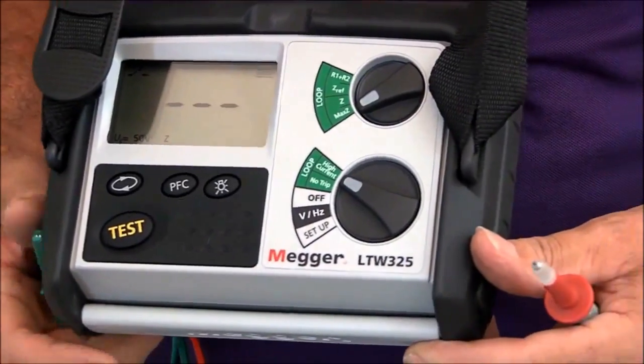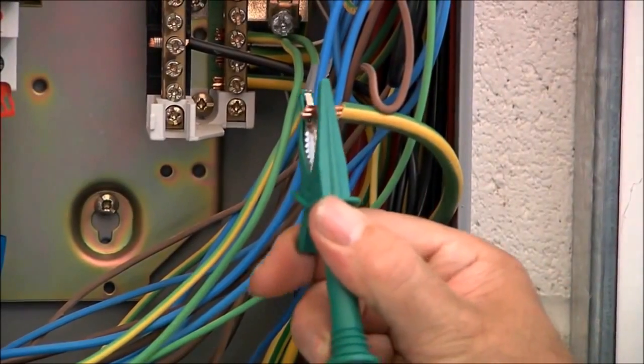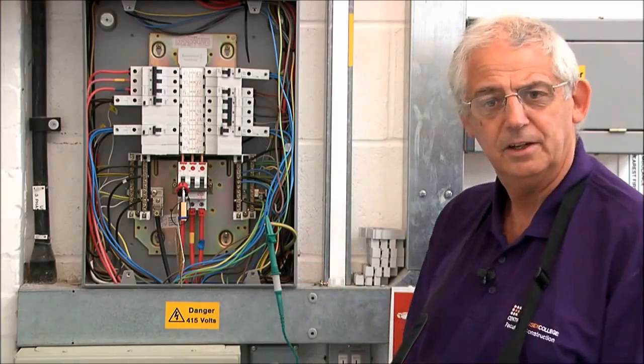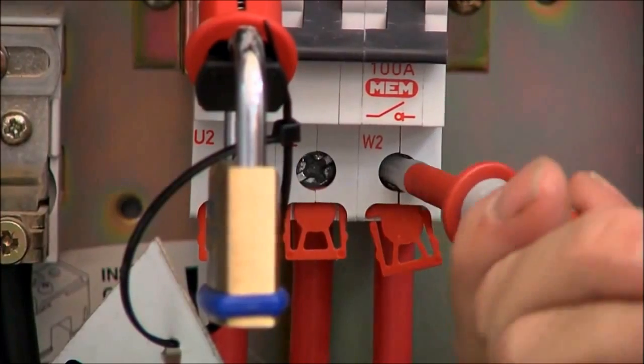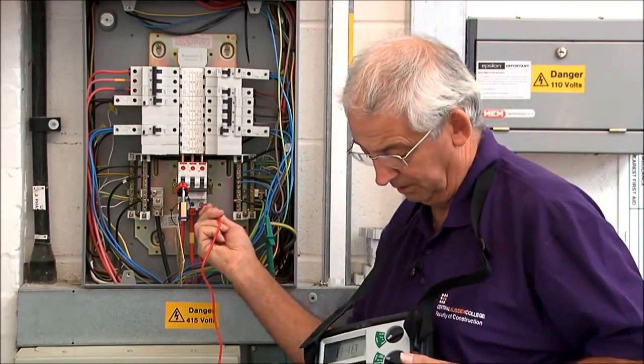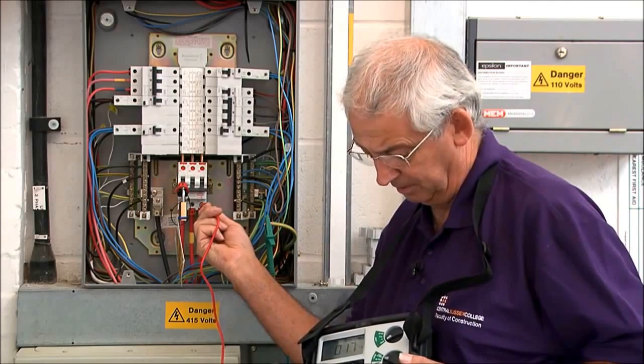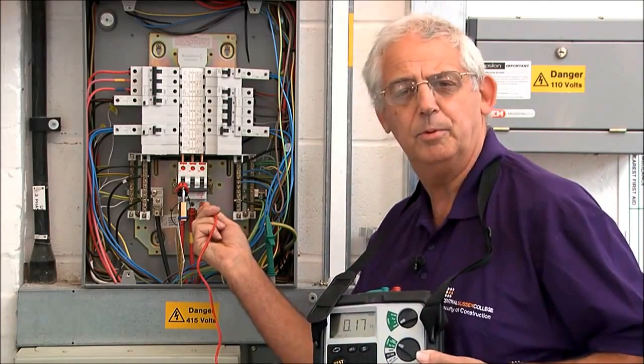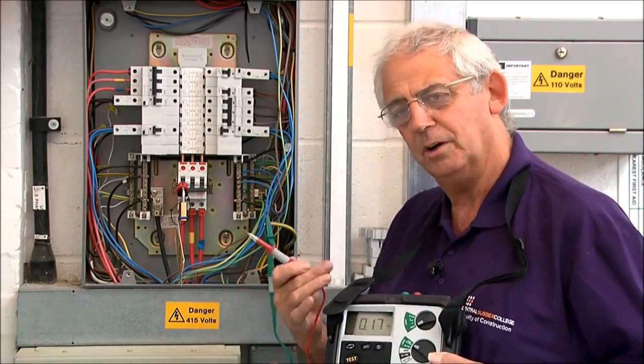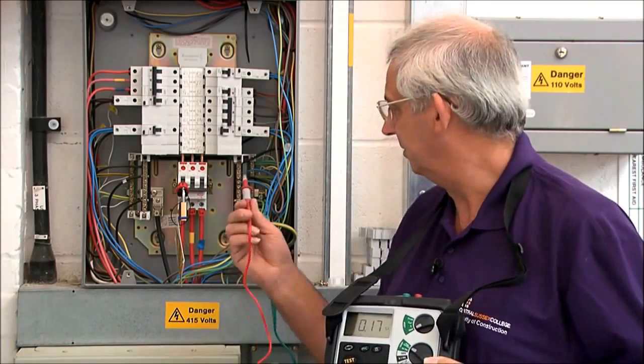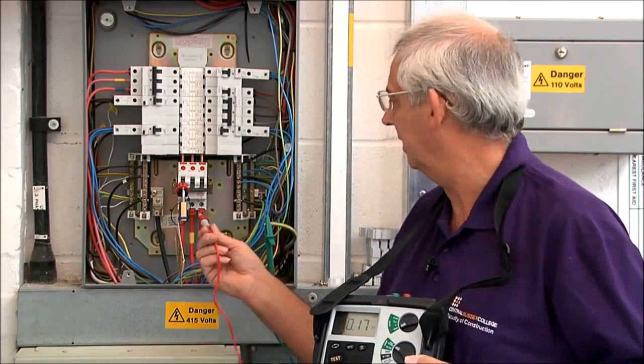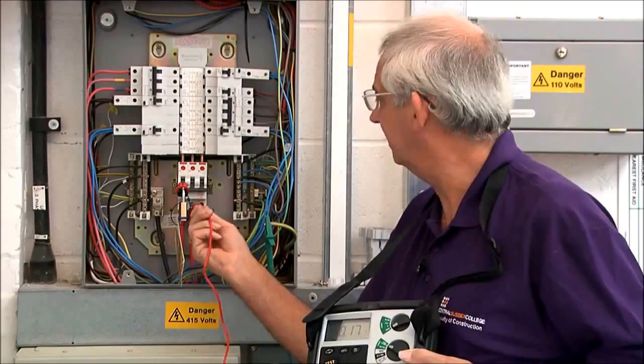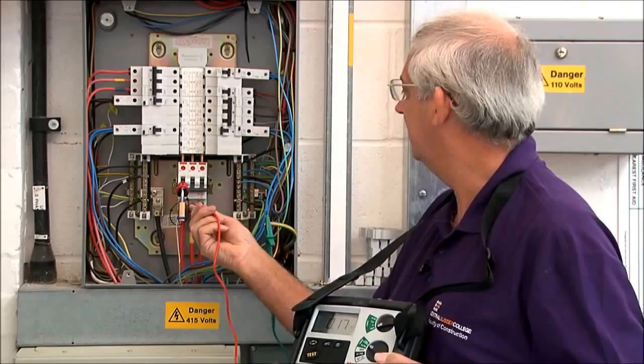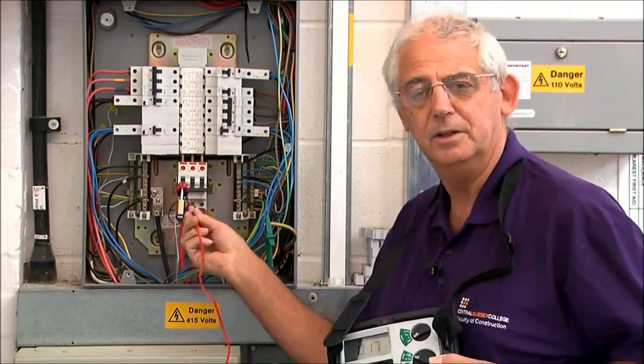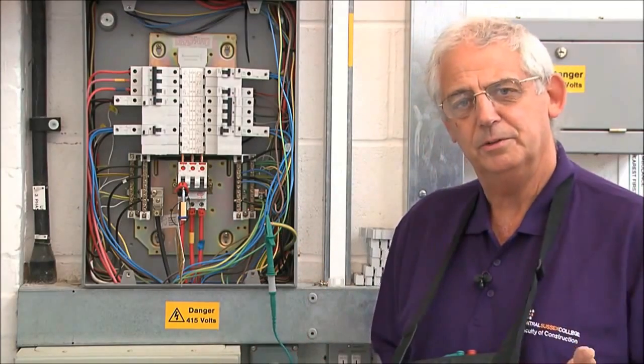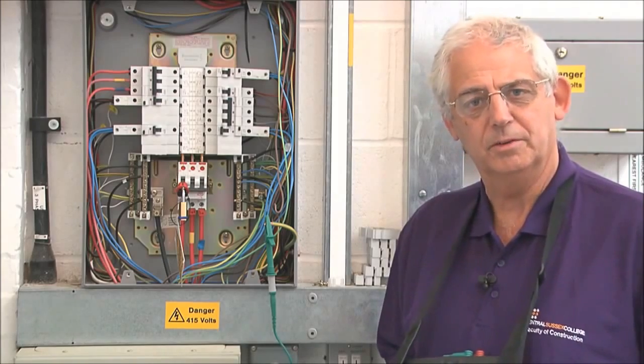I can put this instrument on a high current. I need to connect the crocodile clip to the disconnected earthing conductor and then just test between one incoming line and earth, and I've got a value there of 0.17. But of course I need to know the highest value, so I need to do the test between all three lines. 0.17 and again 0.17. So they're all consistent. So my value of ZE would be 0.17 of an ohm.